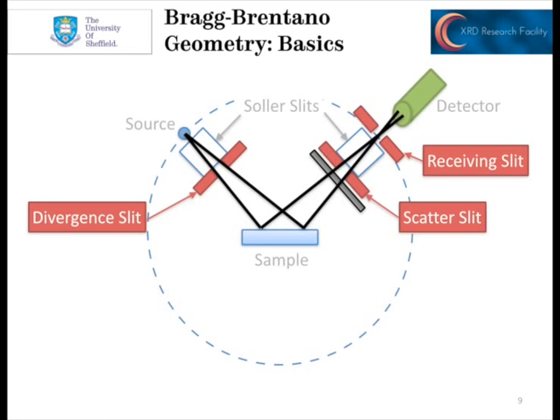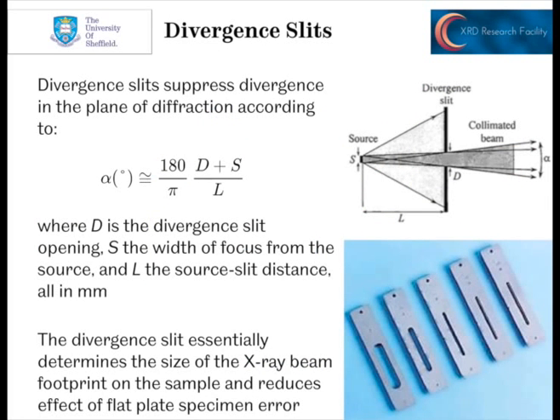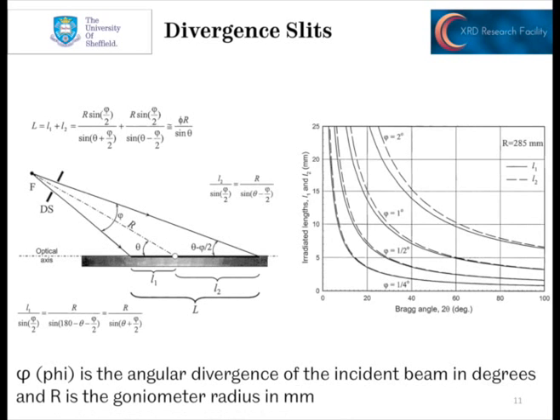We've then got other apertures: the divergence slit on the primary side, and on the secondary side we have scatter slits and receiving slits. The divergence slits suppress divergence in the primary beam, effectively controlling the size of the footprint of the X-ray beam onto the sample. By using smaller divergence slits, we reduce the effect of the flat plate specimen error because we're looking only at those parts closer to the diffraction circle. We can define two illuminated distances: L1 lying between the source and the centre of the sample, and L2 lying between the centre of the sample and the detector. The graph plots L1 and L2 for four common phi settings — slit sizes of 2 degrees, 1 degree, half a degree, or a quarter of a degree.